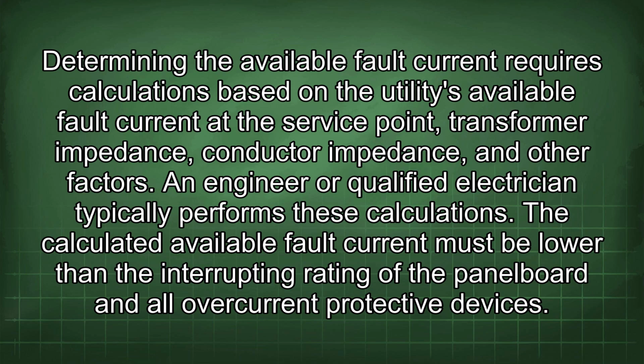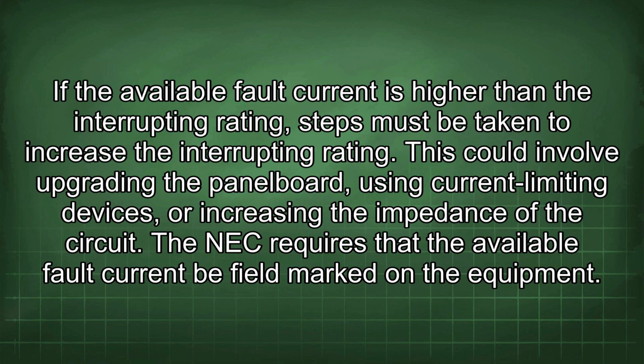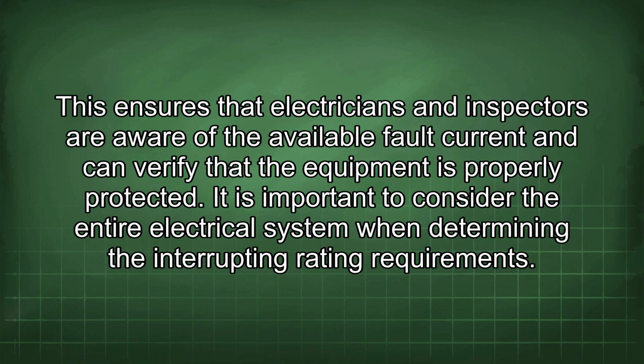The calculated available fault current must be lower than the interrupting rating of the panel board and all overcurrent protective devices. If the available fault current is higher than the interrupting rating, steps must be taken to increase the interrupting rating. This could involve upgrading the panel board, using current limiting devices, or increasing the impedance of the circuit. The NEC requires that the available fault current be field marked on the equipment. This ensures that electricians and inspectors are aware of the available fault current and can verify that the equipment is properly protected.